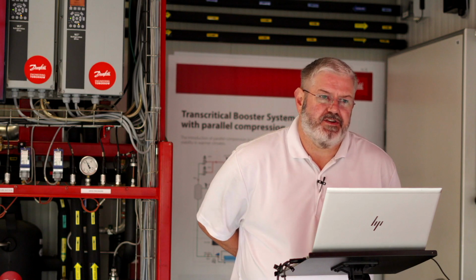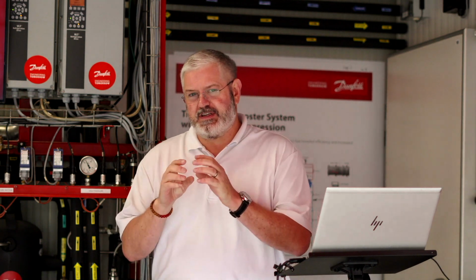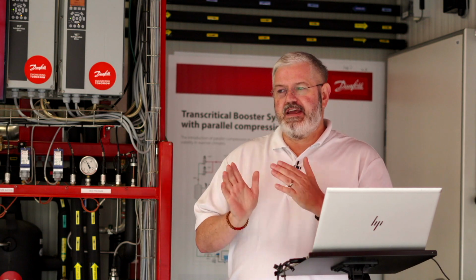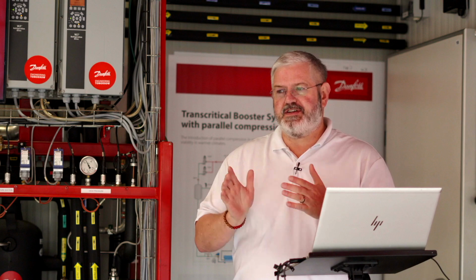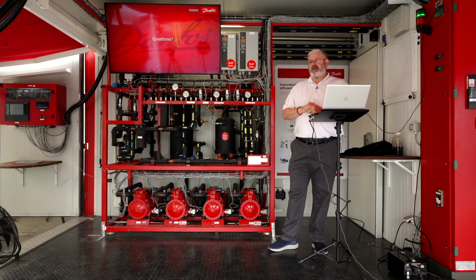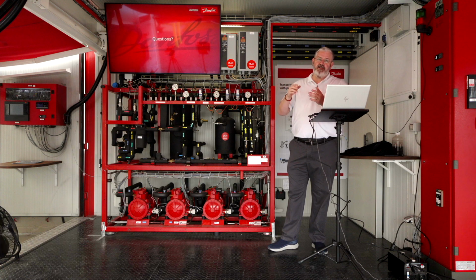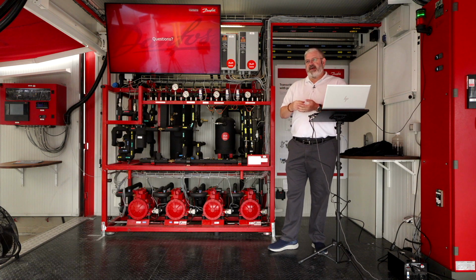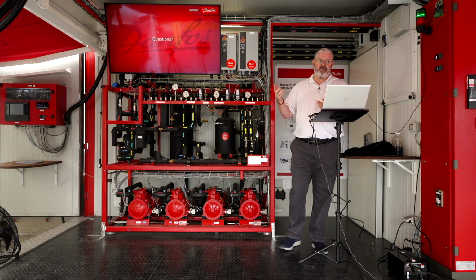Let's see, we have a question. Are the ejector nozzles able to modulate to adapt to load changes, or is it an on-off operation only? It's on-off operation only. I think it's the pressures that high with the small size of the components. It'd be really tricky to get a stepper type situation there, or to even pulse it. They're not even steps. Like the block we have here as an example has 6 cylinders for ejectors. Let's pretend if there were 5 of them, it wouldn't be 20% across the board. It's set up more like 5%, 12%, 17%, so you can build different steps, but it is very limited compared to the 2,500 steps you would see on a stepper valve.